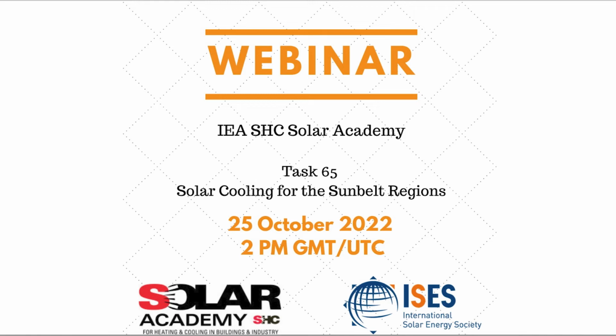Yes, I will. The Sunbelt chiller you saw presented is a fairly new concept, but there are others on the market tackling high ambient temperatures typically found in Sunbelt countries. In particular, there's the hybrid chiller combination—combining vapor compression chillers with sorption chillers, either absorption or adsorption. In both cases, the sorption part, thermally driven by the solar thermal collector, is used to cool down the vapor compression chiller, making it possible to achieve heat rejection for the compressor chiller at 20-25 degrees Celsius. So with high ambient temperatures above 40 degrees, the overall efficiency, the EER, is much better with this combination than running a conventional compressor chiller alone.